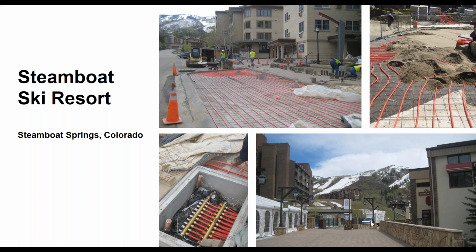So definitely between the pipes, kind of centered between your spacing there, is where you'd want to be. Some other things that can be tricky there: you definitely don't want it under an awning. You don't want it under a spot where maybe a truck would park and then could shield it from catching the snow all night. That could be an issue. But really, you want to put it in the most critical part of this space.